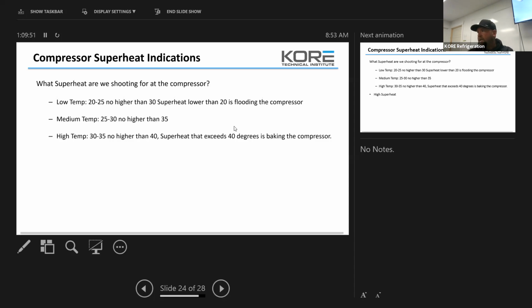So you need to understand that and take care of it. There are a lot of times I'll use high temp application compressors in low temp applications, because high temp compressors are sometimes a little more robust, when you're dealing with can compressors and scroll compressors. You'll see high temp application compressors used in a low temp setting, it's just what the engineer decided to do. But you need to understand those variations: changes have been made to the internal components for the application. And that's why, when we're doing HVAC, we don't look at superheat at the compressor, because you're probably going to be over 40 a lot of times.